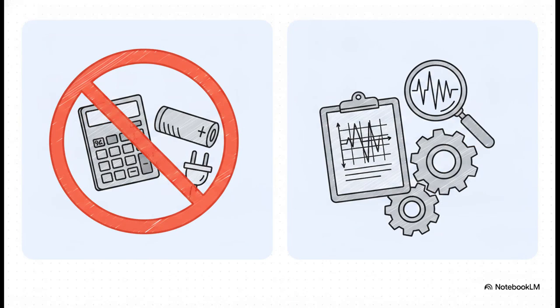We have to start by busting the absolute biggest myth in our industry. You know the one. The idea that choosing a hospital UPS is just a matter of walking into a room, adding up the wattage on the equipment nameplates, and throwing in a lazy 20% safety margin. Look, that's how you set up a battery backup for your home office, not a life-saving medical facility. The reality is much more intense. Proper UPS selection requires rigorous clinical risk assessments, extracting precise transient data from manufacturers, and complex system integration. It's a highly engineered ecosystem.